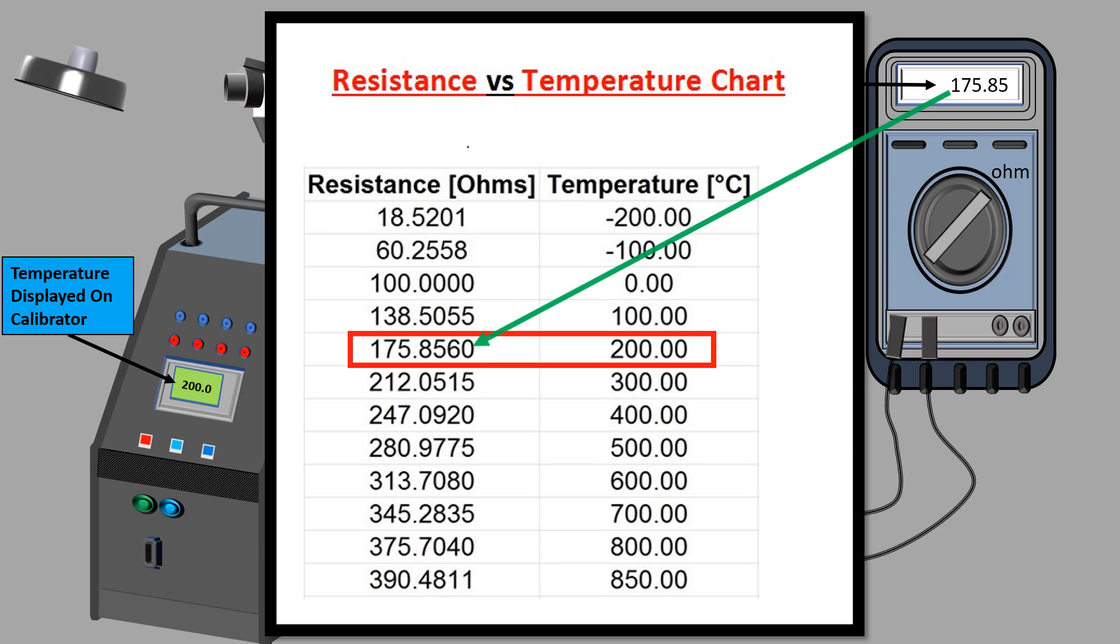If both the temperatures displayed are the same or within acceptable deviation from the standard value, the RTD is considered to be accurate.